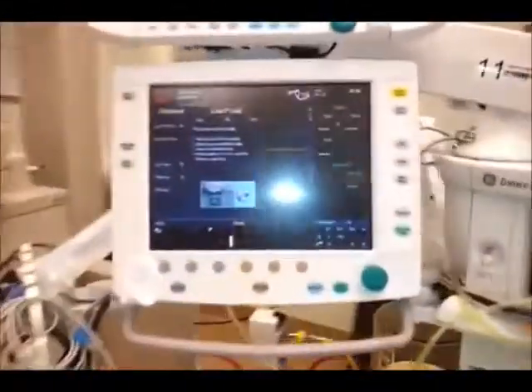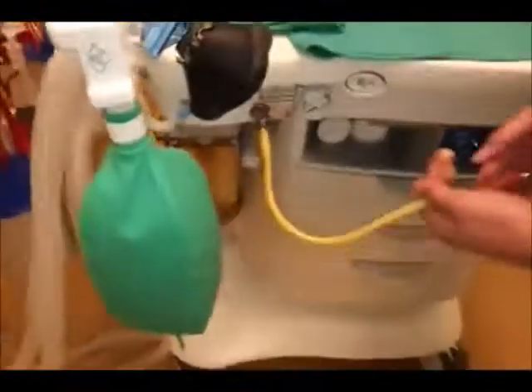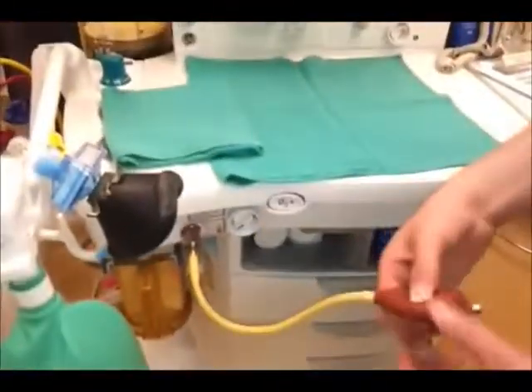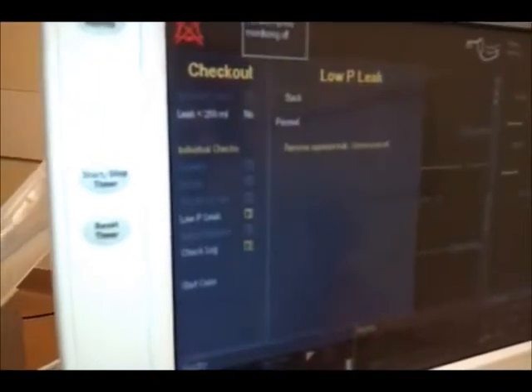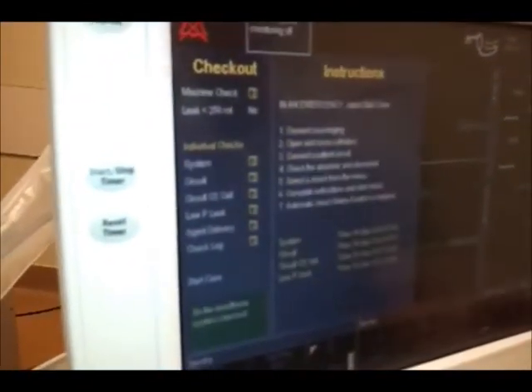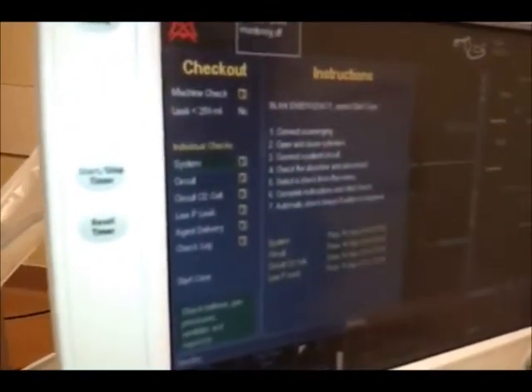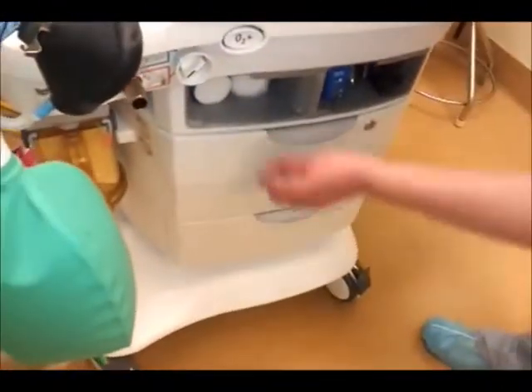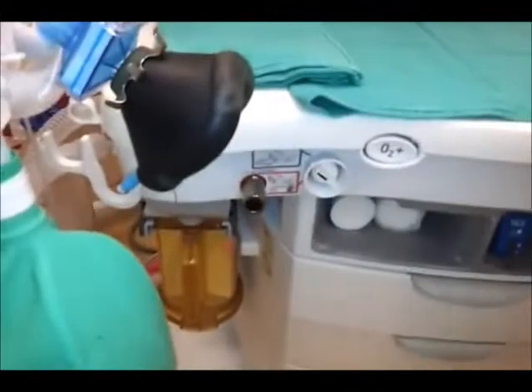So the 30 seconds is probably up. So yeah, it's been a minute. And the bulb's still pretty deflated. So all you have to do is hit pass. And that's the low pressure leak test. You flick that off on the gas machine checklist. So you don't need the bulb anymore. After you've done that, you're going to switch it back to the circle system.